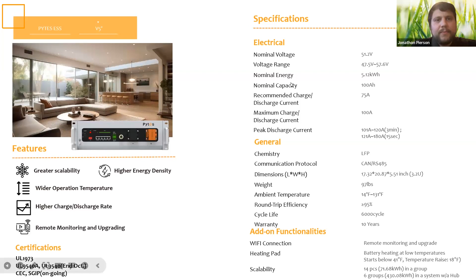We have an accessory called the hub. With the hub, we're able to have, with the eBox 48100R series, each group as a maximum of 8 batteries in one group, as illustrated on this slide. The hub allows us to combine and communicate with 6 different groups. This gives us a total of 48 batteries, which is 245 kilowatt hours of energy, all closed-loop communicating and acting as one system in close proximity, which is amazing.